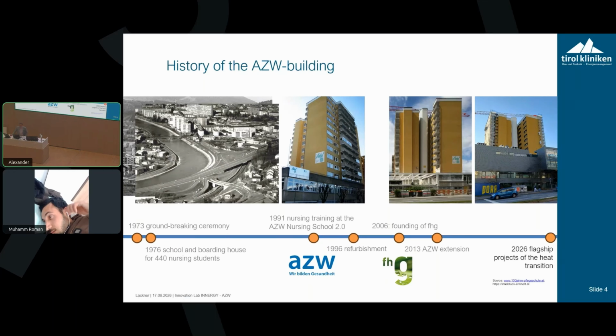So about the history, as I told, for the Olympic Games, the buildings were built, and beginning at 1990, it was a nursing training school for the Tirol kliniken, and afterwards there were installed the FHG. It was Fachhochschule Gesundheit, and therefore there was an extension of the classrooms in the basement, and the tower was in the building quality from 1976. Some windows were changed, but not all. They have uncontrolled ventilation through the windows. They have only, I think, about 4 centimeter insulation at the walls and no insulation on the roof. And so it was a very bad thermal quality.